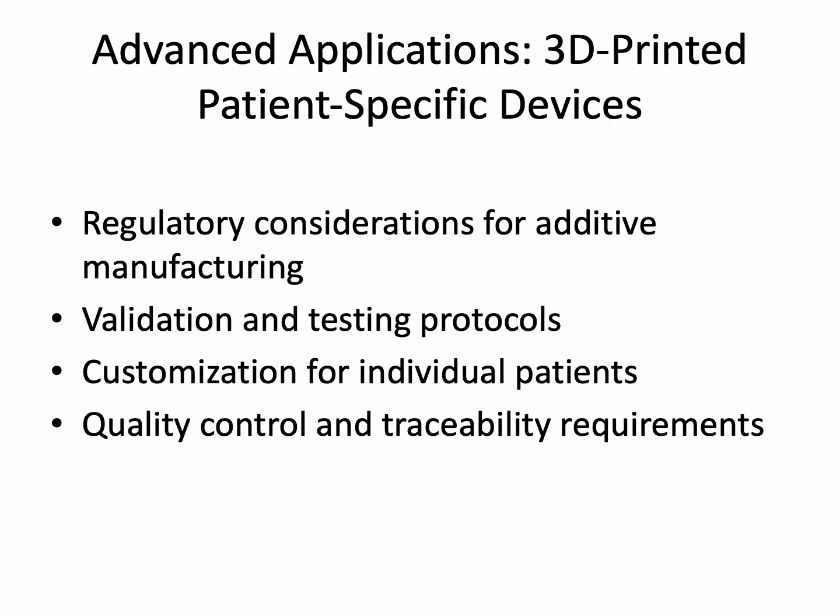3D printed patient-specific medical devices introduce regulatory complexities due to customization and additive manufacturing processes. Regulators require detailed validation protocols for printing processes, material properties, and sterilization. Design and clinical justification for individual patient-specific devices must be documented, including risk management for variations in geometry or fit.